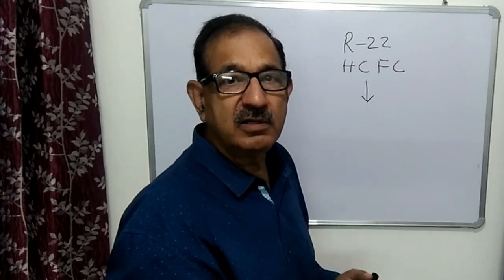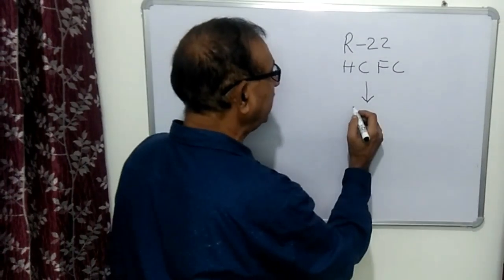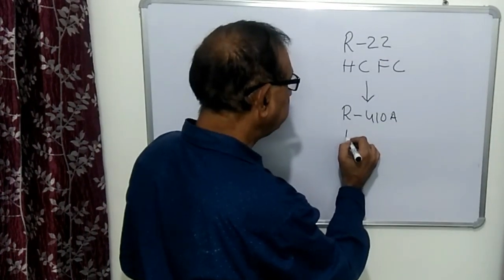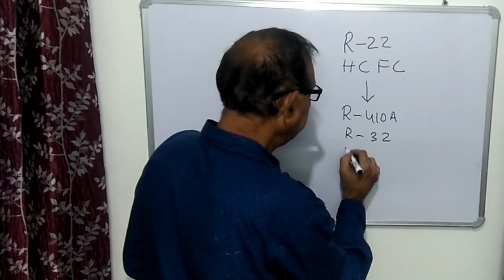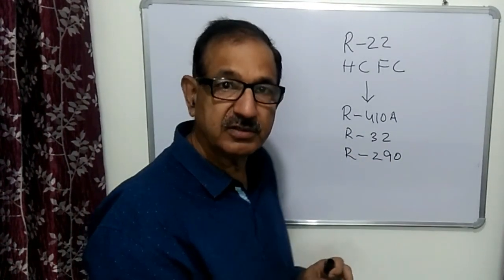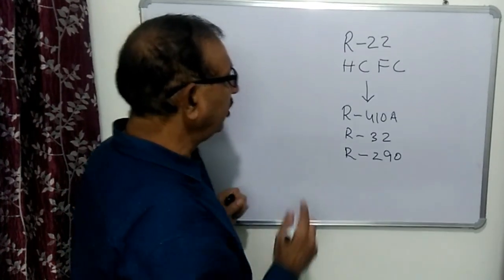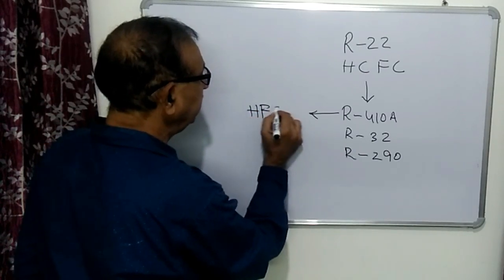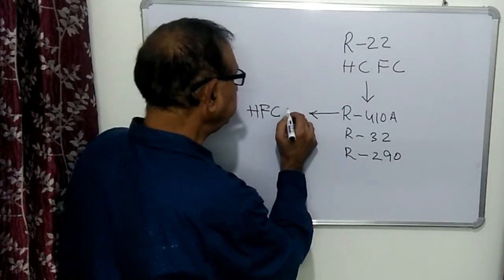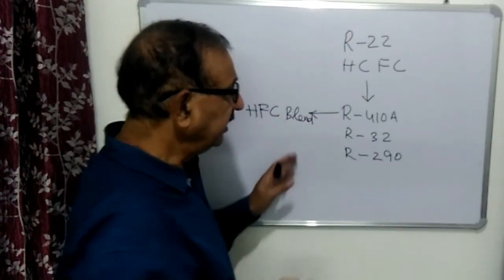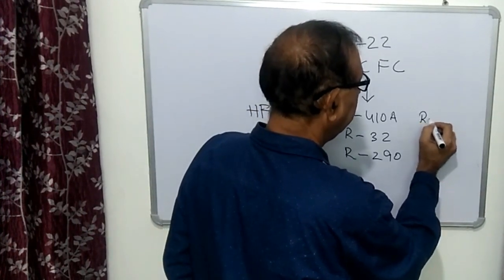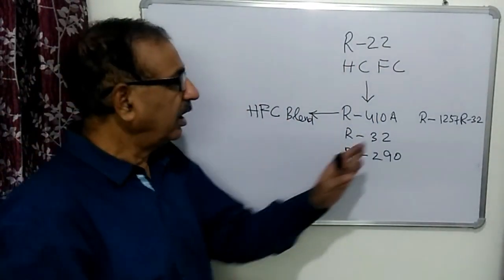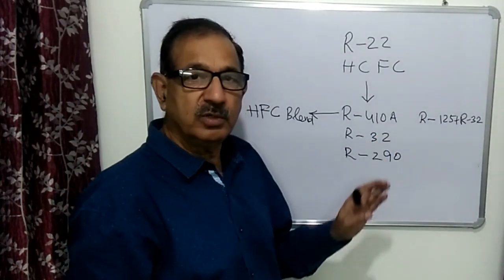Since we are not going to have R22 in the future, the alternates we have are R410A, R32, and R290 for air conditioners. R410A is an HFC — hydrofluorocarbon — and it is a blend. It is a mixture of R125 and R32.